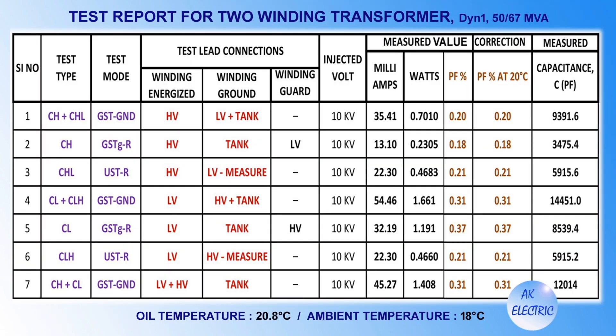This is the test report for a 2-winding transformer — a 67 MVA transformer test report. One can observe that this test was made at an oil temperature of 20.8 degrees Celsius and ambient temperature of 18 degrees Celsius. In the next slides we will analyze the test report part by part.